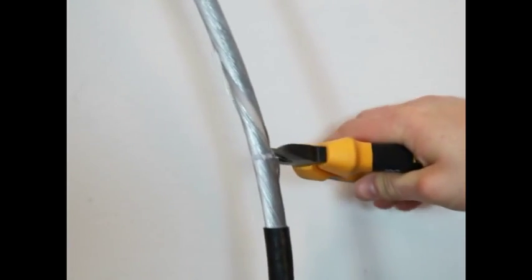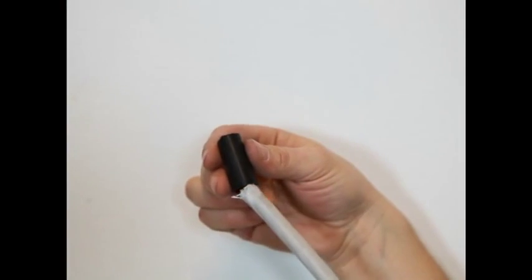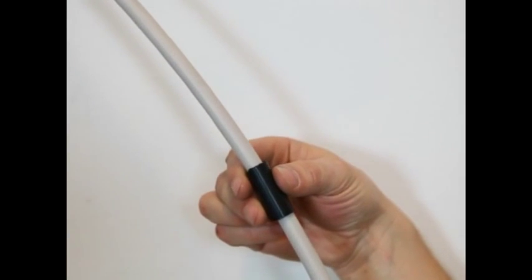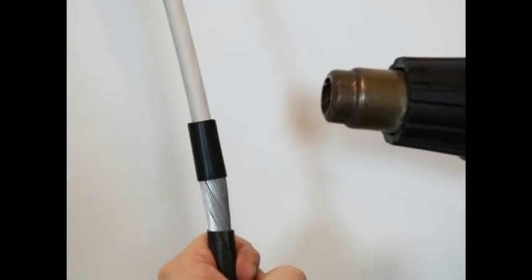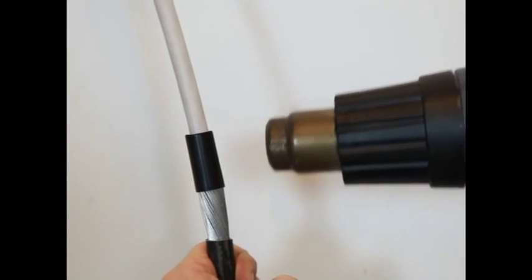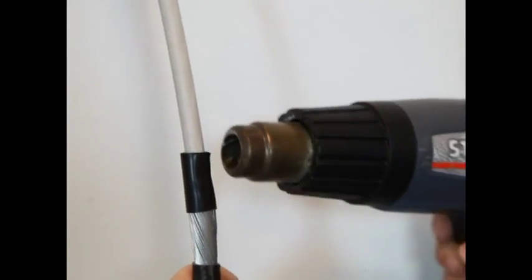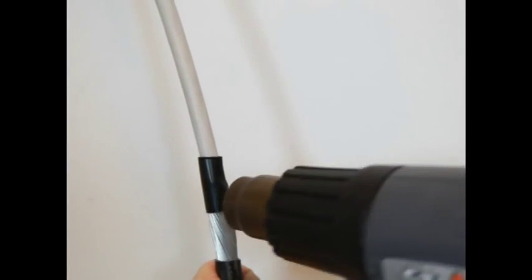Cut the armor. Cover the end with a piece of shrink tube. Use a hot air gun to shrink the tube. Make sure that the shrink tube is completely outside the module.